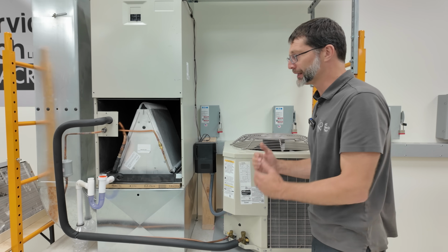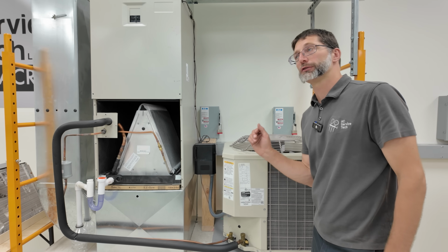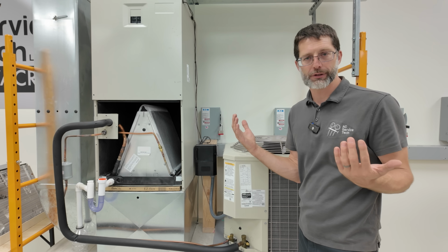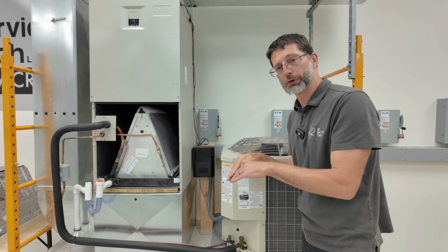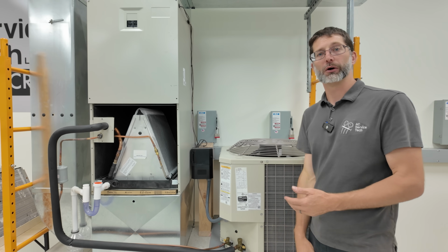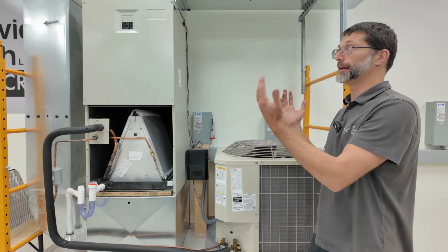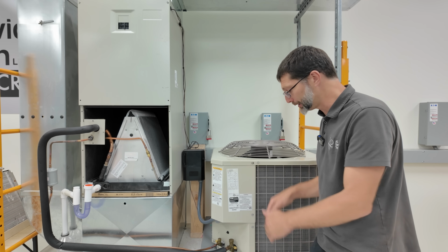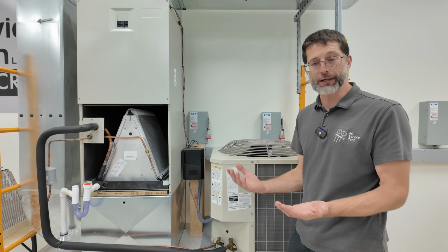The whole point of the zinc coating on the microchannel coils is to be able to have lateral corrosion. It's like a sacrificial anode almost. It wants lateral corrosion instead of inward corrosion, where an inward corrosion would end up having a refrigerant leak. So you've got to think the outdoor unit of an air conditioner is higher pressure, and it's in a salt air environment or maybe an acidic environment where you have leaves going down in there, and you may have a problem at the lower section due to leaks.